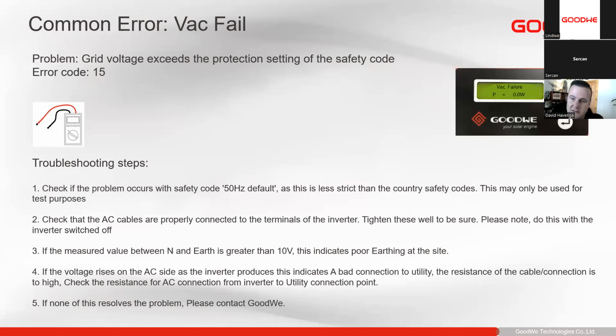So it could be the cables we are using are too small, or I've seen the cable have the right size, but unfortunately the cable had a fault somewhere and caused a resistance, which over time would have burnt the cable, but the inverter's voltage would rise the whole time and then it stops producing. So the inverter always puts a slightly higher voltage out than the utility, so that voltage starts to creep up if we cannot get the power away.